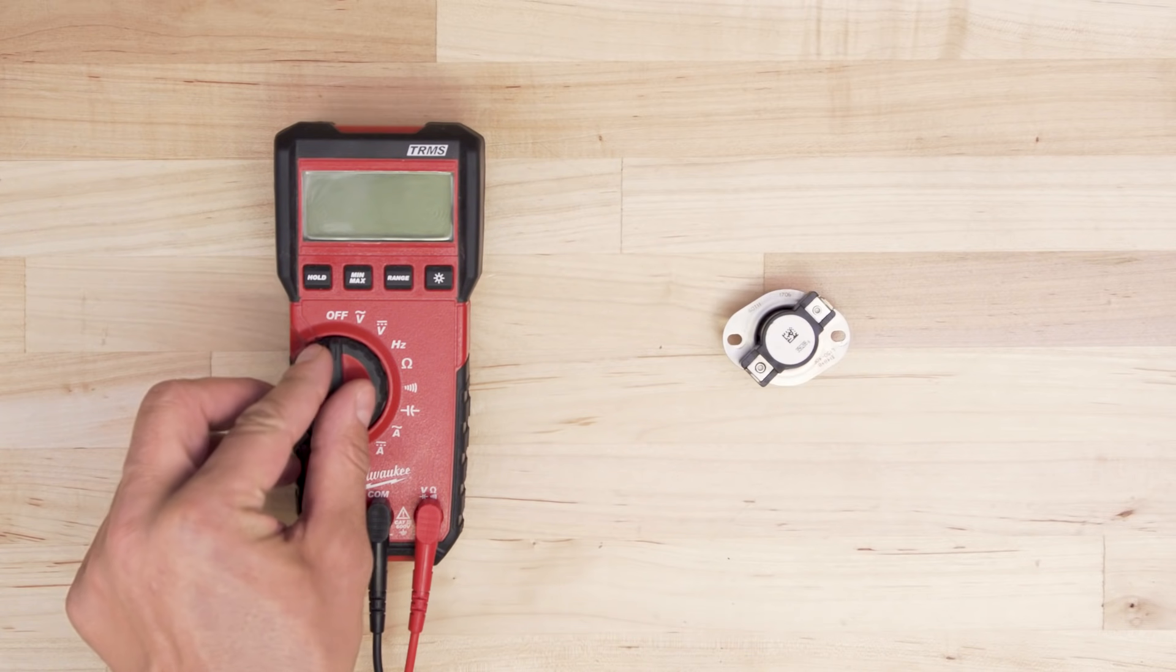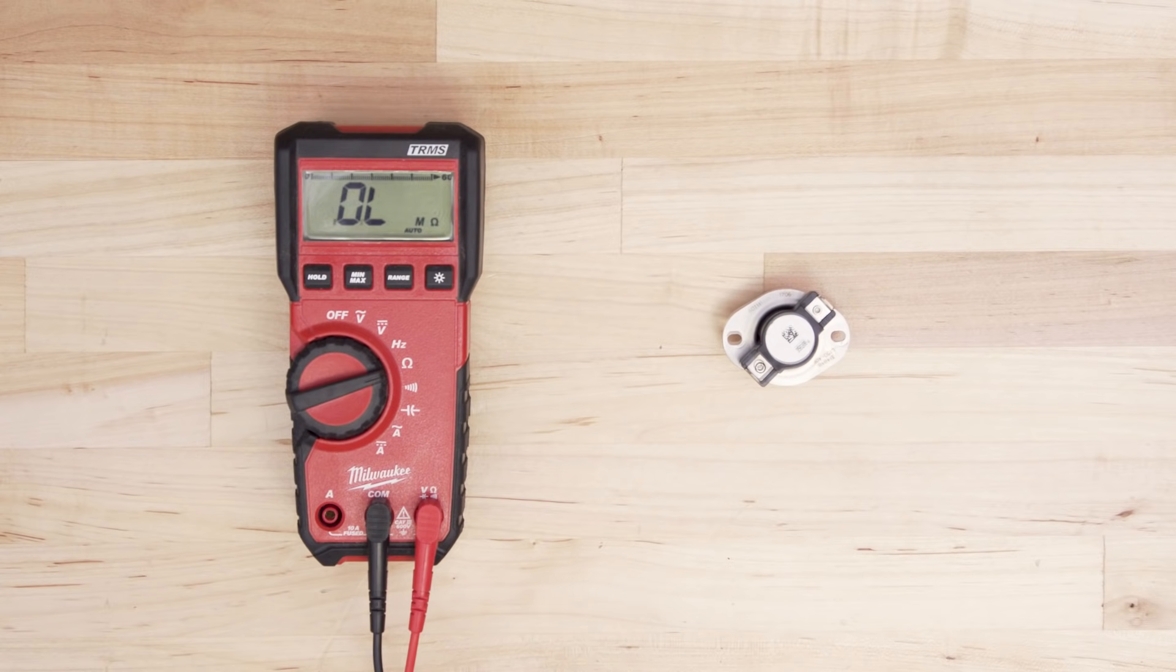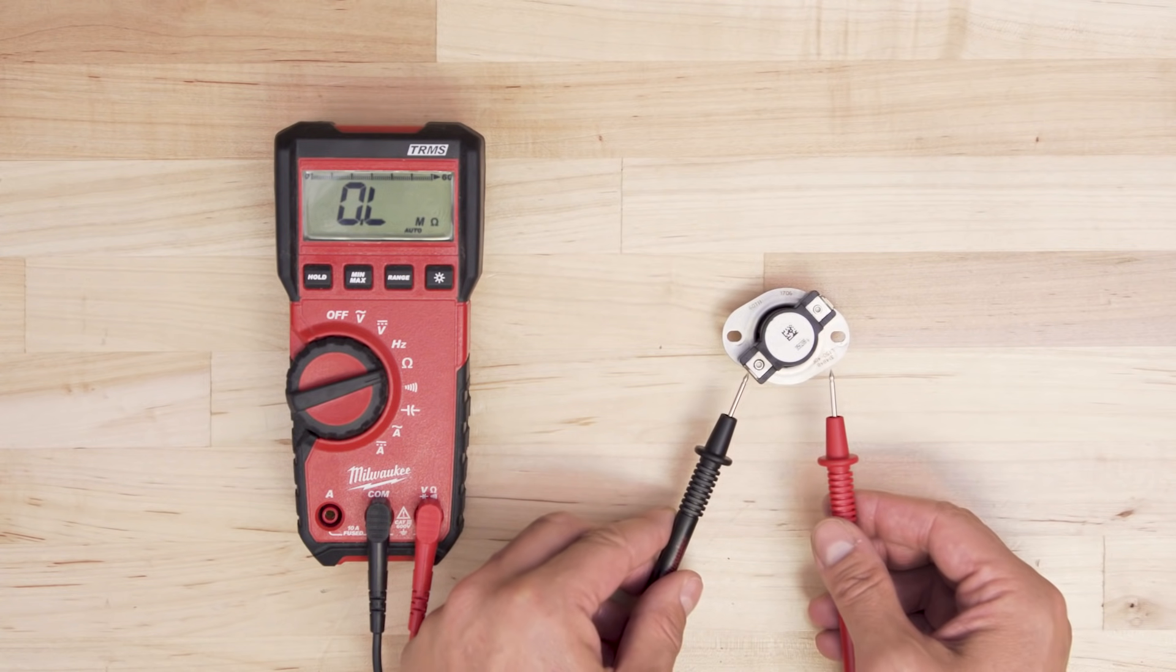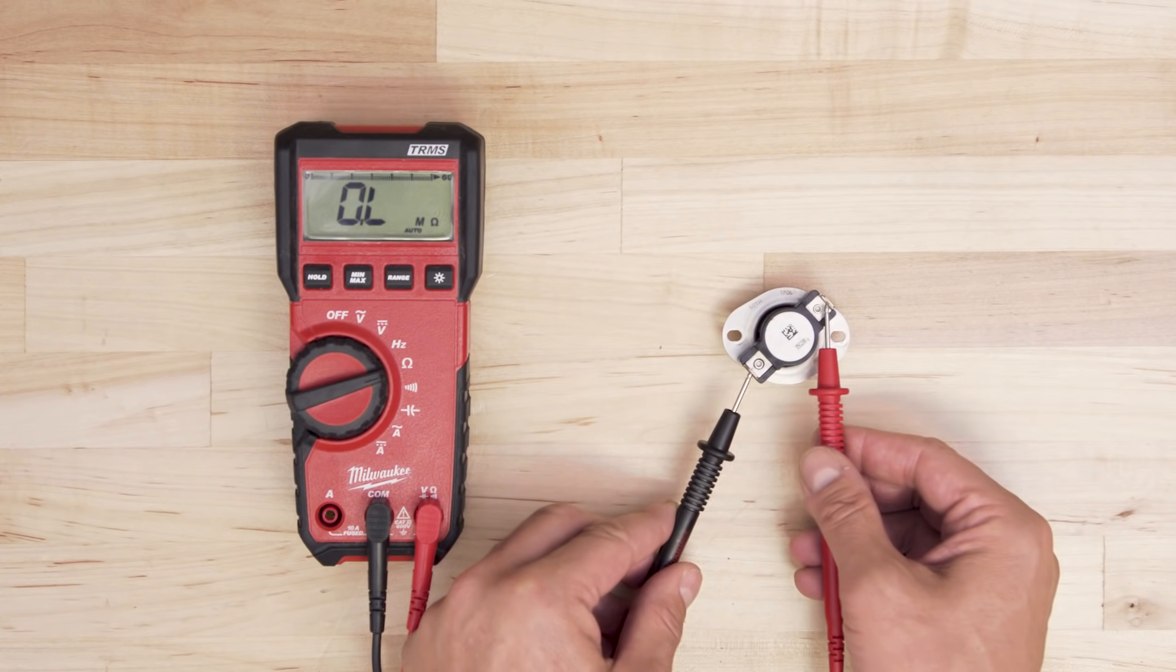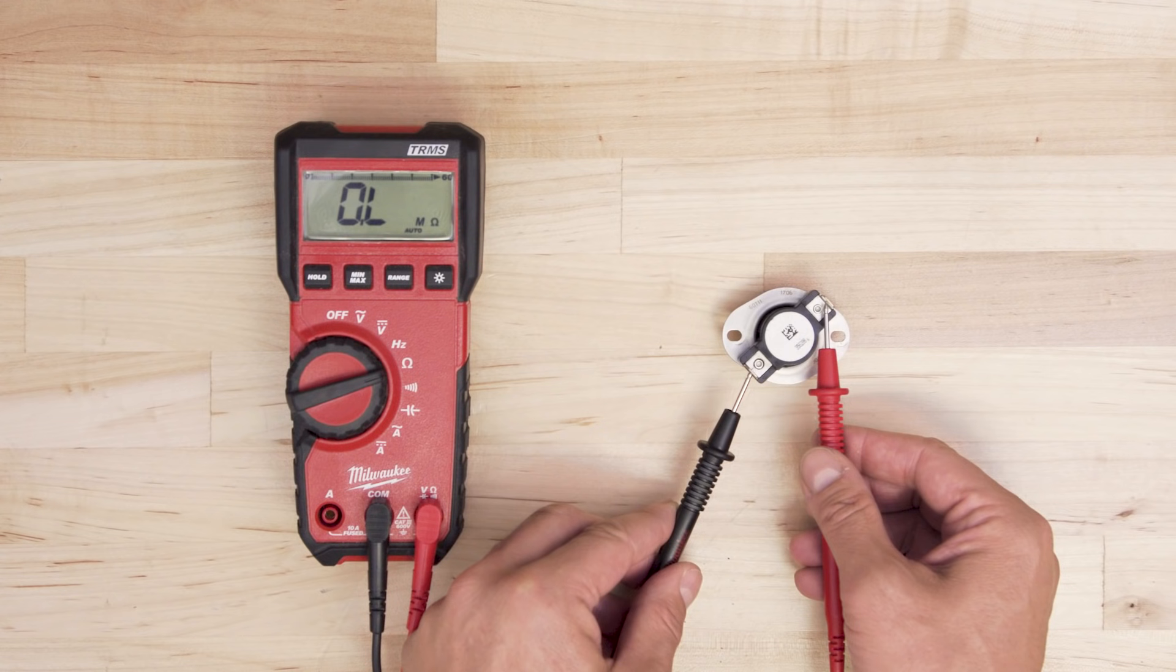Take the multimeter and set it to the lowest ohms of resistance. Now touch the probes to each terminal. If the switch has continuity then the multimeter will show zero ohms. If the switch is open or faulty then the multimeter will show infinite resistance. If there is no continuity then replace the limit switch.